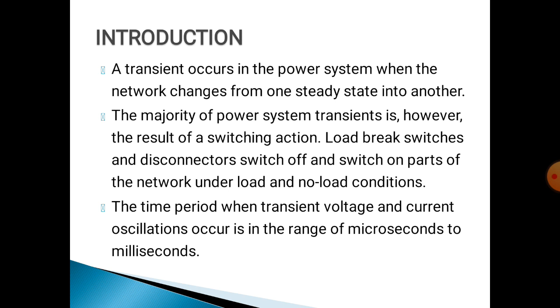Switching surges are nothing but the making and breaking, that means on and off, of electric circuits with switchgear, which may result in abnormal transient overvoltages in power systems having large inductance and capacitance values. The transient period is very short, in the range of microseconds to milliseconds.